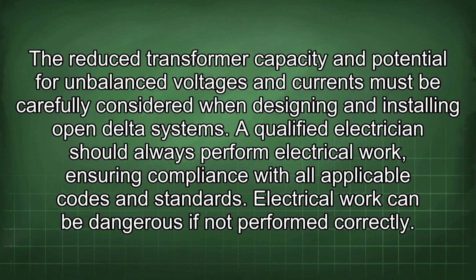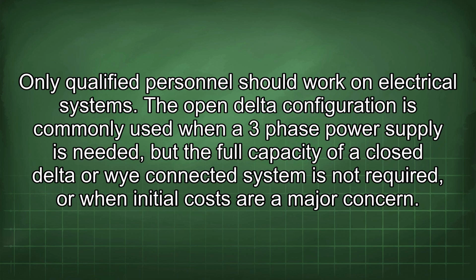Electrical work can be dangerous if not performed correctly. Only qualified personnel should work on electrical systems. The open delta configuration is commonly used when a three-phase power supply is needed but the full capacity of a closed delta or Y-connected system is not required, or when initial costs are a major concern.